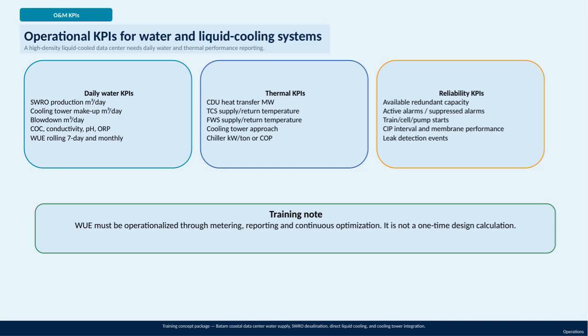Let's delve into the key operational and maintenance KPIs for water and liquid cooling systems in a high-density liquid-cooled data center. These facilities require daily tracking of water usage and thermal performance to ensure efficient and reliable operation. Starting with daily water KPIs, we monitor crucial metrics like the production volume of seawater reverse osmosis, or SWRO, measured in cubic meters per day. We also track the amount of makeup water added to the cooling towers, blowdown volumes, and key water quality parameters such as cycles of concentration, conductivity, pH, and oxidation reduction potential. Importantly, water usage effectiveness, or WUE, is calculated on a rolling 7-day basis, as well as monthly to identify trends and opportunities for improvement.